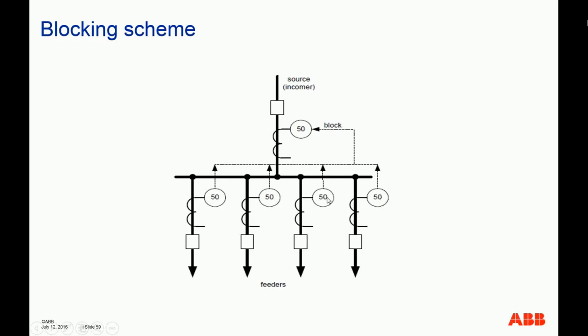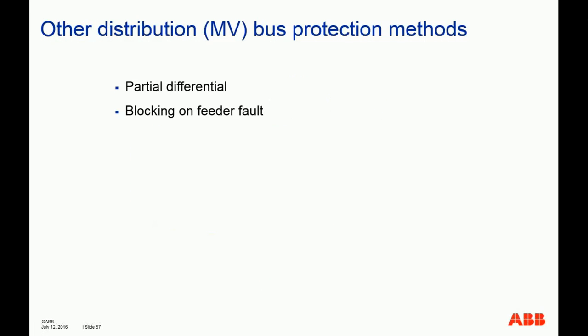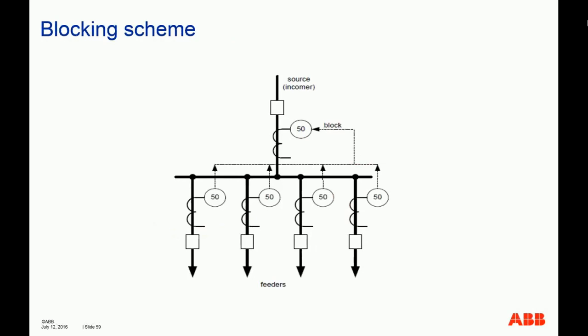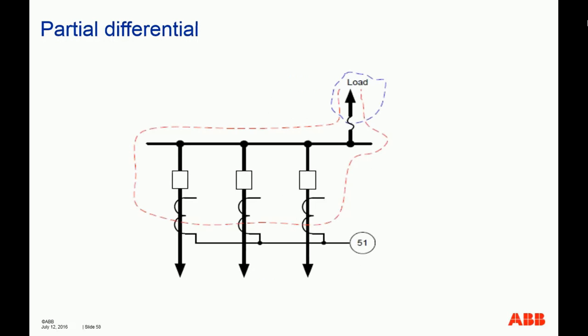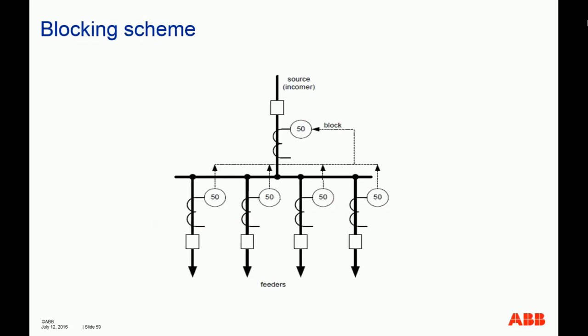Whenever a fault happens, that's why we call it a blocking scheme. Whenever the fault happens on the feeder, sensed by any of these devices, you will close the output and then send a signal to the input of the main incoming relay, so as to block the operation. If the fault is on the bus, and assuming there's no backfeed from the feeders, then these 50 relays will not sense or detect the current, so they will not send any blocking signal to the main incomer relay. In that case, the incomer can trip with a certain time delay for safety margins.